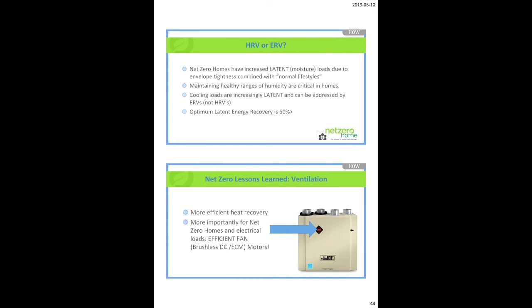So, net zero, again, let's talk about humidity control, because we're on ventilation. This is, again, why this is so important. Relative humidity is what we're finding out to be the real big issue with health in these low load homes. Robert Bean would say, along with ASHRAE, 35% to about 40% in the winter. In the summertime, maybe as high as 55%, but somewhere in that range, because if you get too high or too low, you are at risk of a lot of different things.